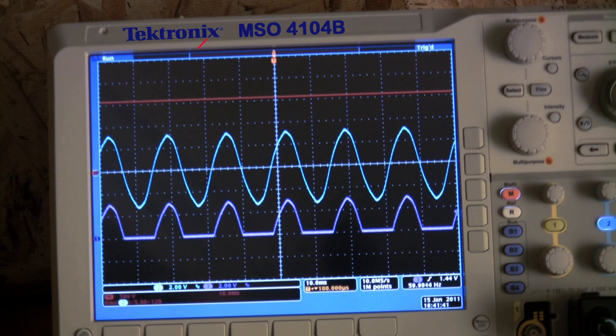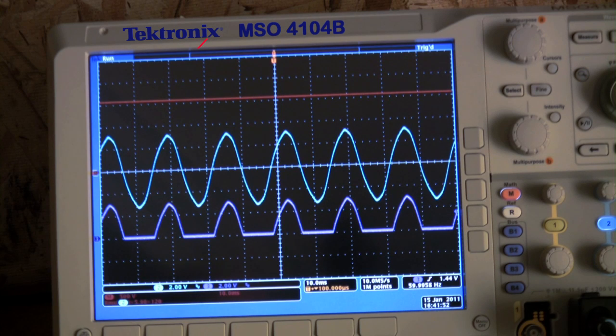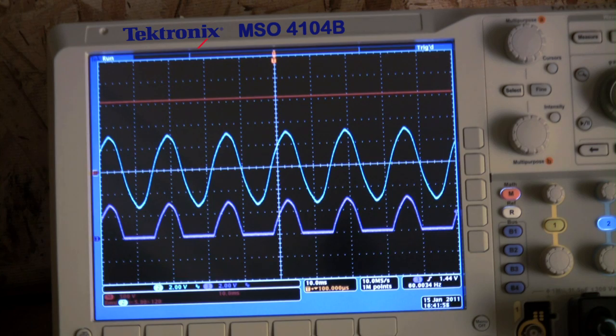The top trace makes use of the built-in waveform math capability of the oscilloscope. The scope calculates the RMS value of the current waveform, scales it, and multiplies it by the RMS voltage and displays it as a DC value. At 500 watts per vertical division, it's measuring a little over 1500 watts, which is the correct value for my shop heater.